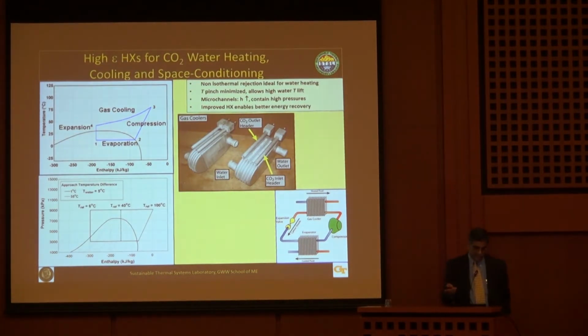I was talking to Professor Koyama yesterday, and I said that we've developed these CO2 gas coolers. Instead of the simple tubes used by one of the Japanese manufacturers, we came up with microchannel configurations where we cleverly arranged the tube orientations so that, even though they are cross-flow heat exchangers, they behave like counterflow heat exchangers through pass arrangements.